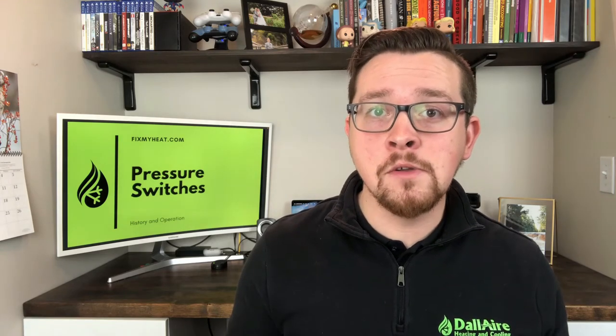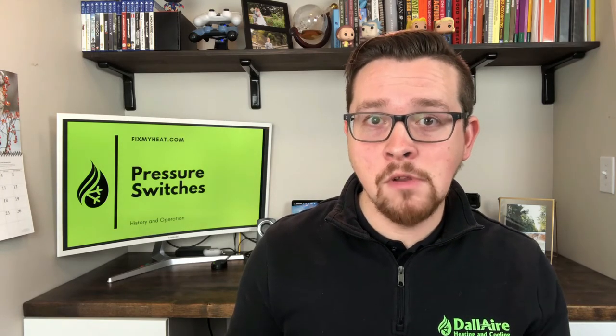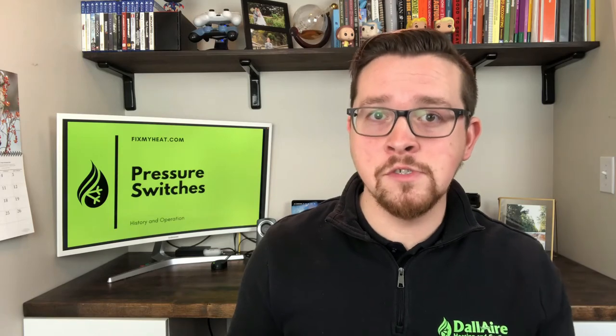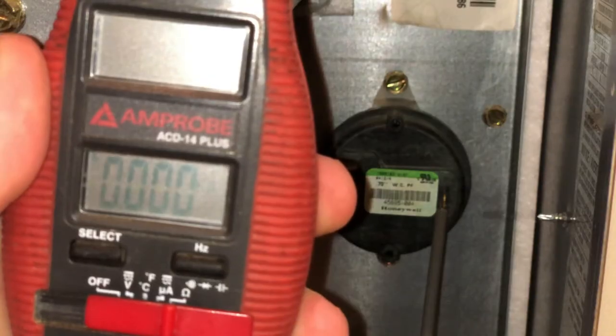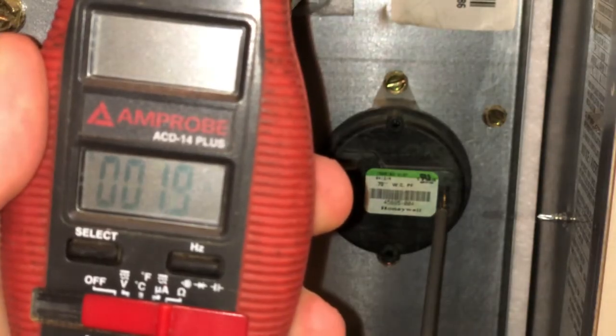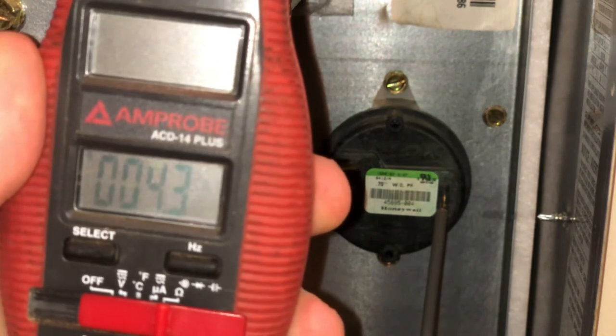You can also close the pressure switch manually by either blowing or sucking on the tube to cause that bladder to pull in or move out and close those electrical connections. You can then ohm out that switch to see what the resistance is through it. And if it's high, you might need to replace that switch as well. Don't blow or suck too hard because you don't want to tear a hole in that bladder.